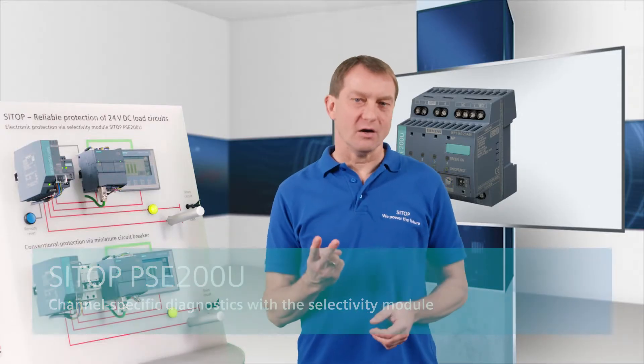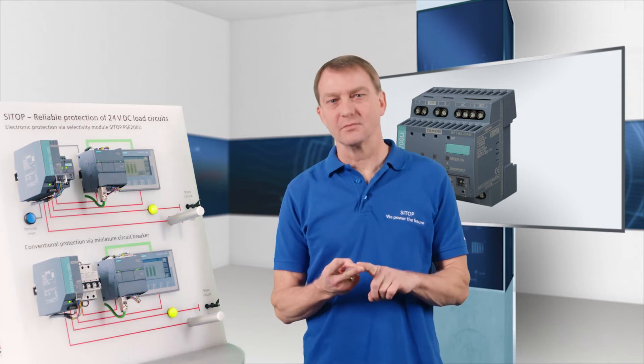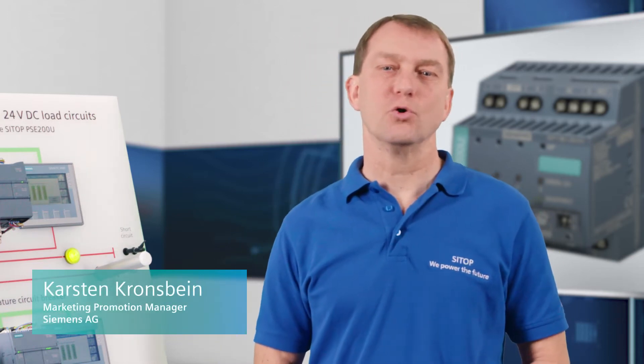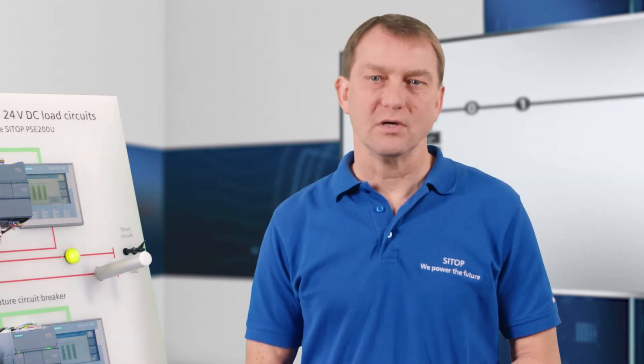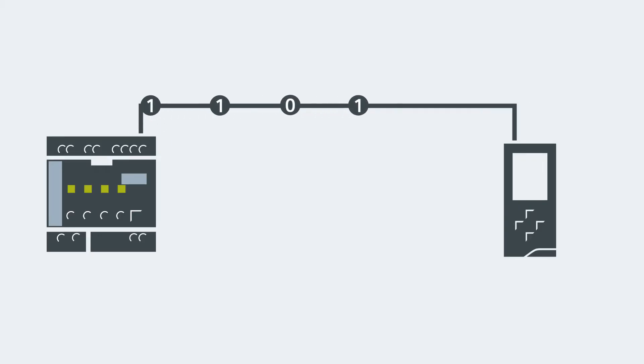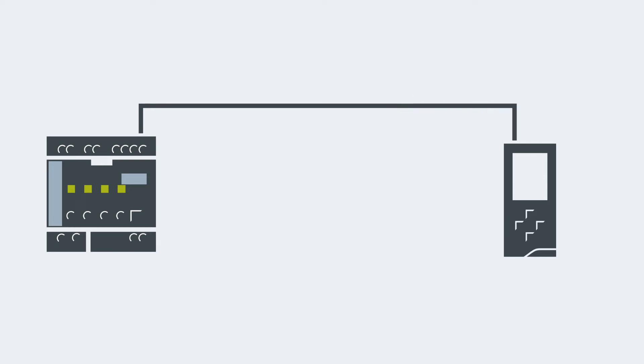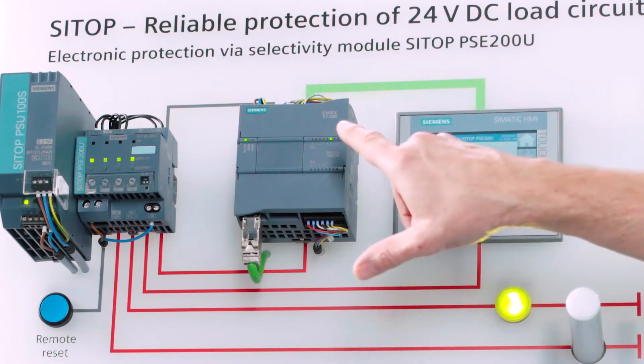Two versions of the Selectivity module are available for output diagnostics: one with common signaling contact and one with single channel signaling. The common signaling contact indicates that at least one output has switched off due to a system failure, and evaluation is performed by using a digital input in the PLC. If channel-specific diagnostics are required, single channel signaling is the smart alternative — only one digital input is required, and a serial code is evaluated by an S7 function block.